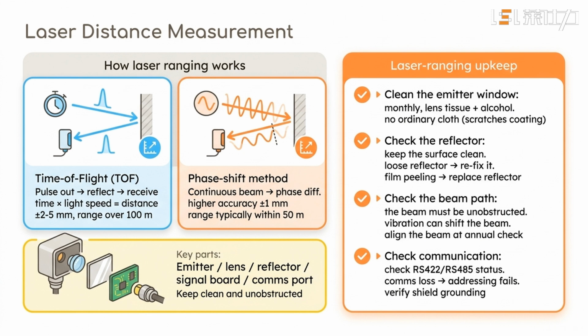Let's look at laser ranging. The principle is simple. The laser head fires a beam at the reflector opposite and back, and the flight time gives the distance. It has 2 key parts: the emitter window and the reflector. The window must stay clean, but mind how you clean it. Always use lens tissue and absolute alcohol, never an ordinary cloth, which scratches the coating. Keep the reflector clean too, and replace it if the reflective film peels off. Also make sure nothing blocks the beam path. Vibration can shift it, so check the alignment at the annual inspection.